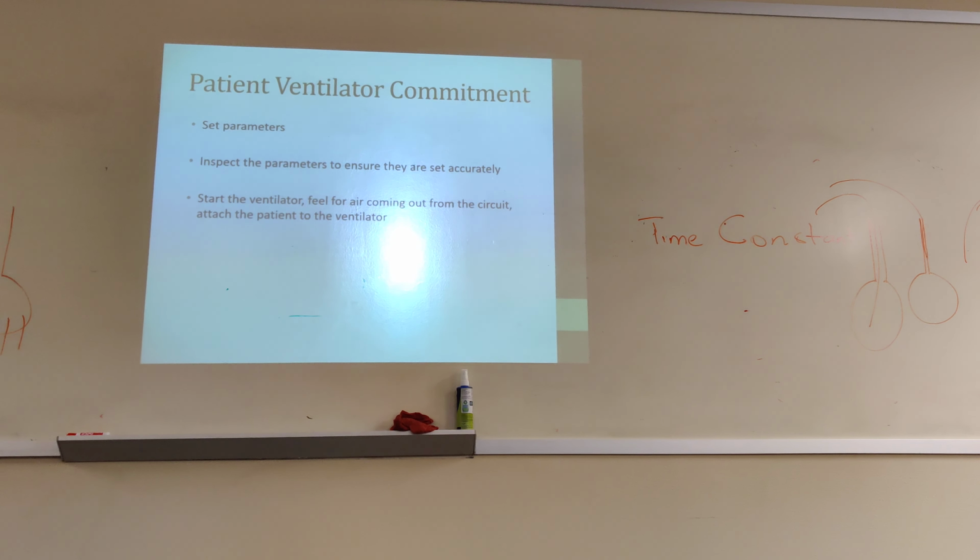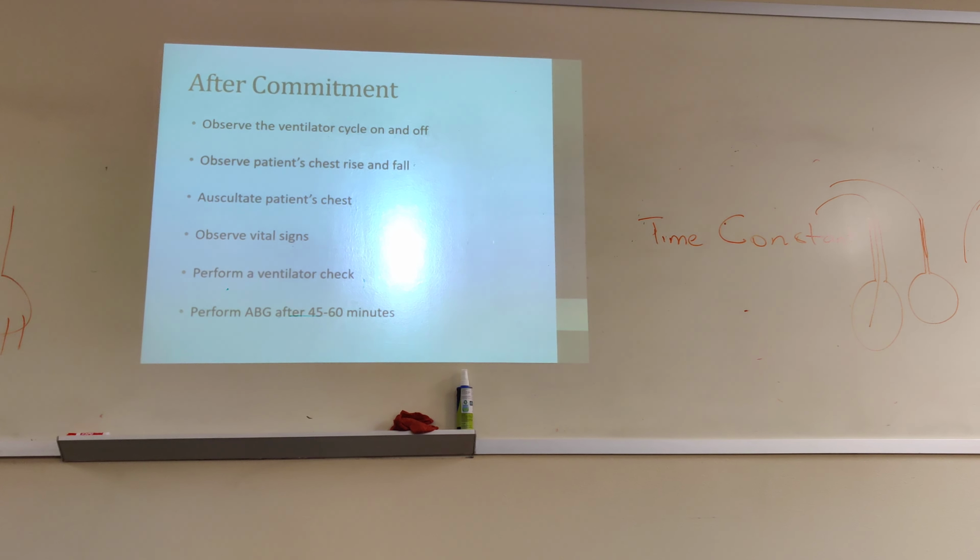Okay? Start the ventilator on. Feel for the air coming out. Just because you turn it on doesn't mean that it's working. Maybe it will start to malfunction when you turn it on. So you turn it on, you feel for the air coming out, and then you attach your patient. But you don't go home after that. You're not done yet. Okay, you can't say, well, I'll see you later.